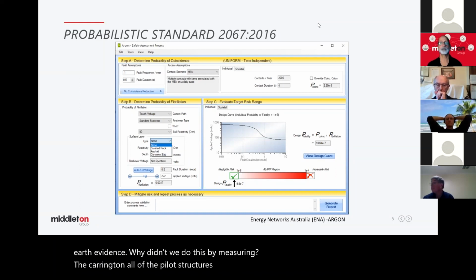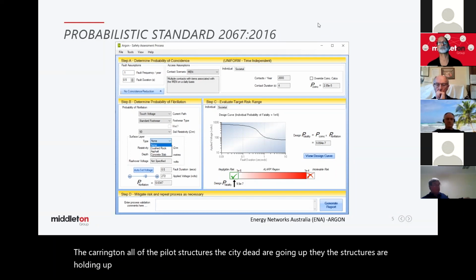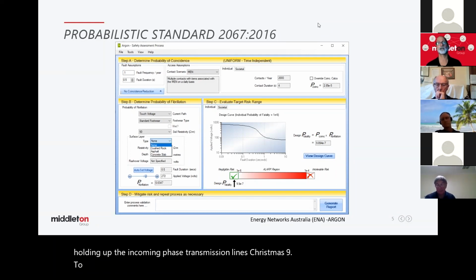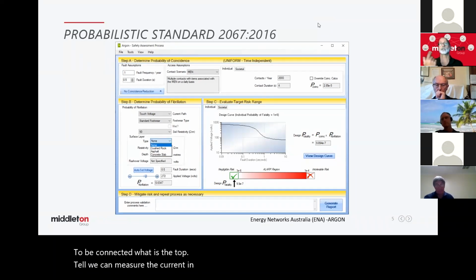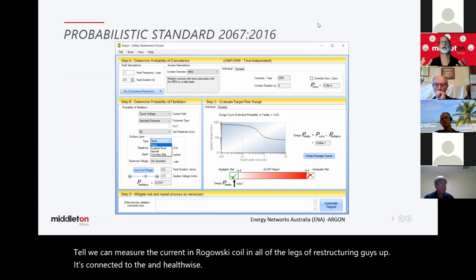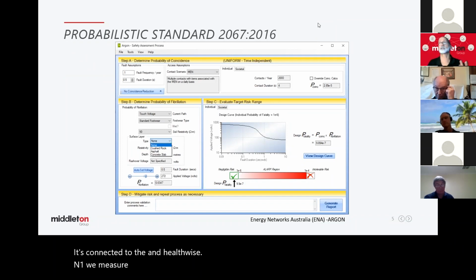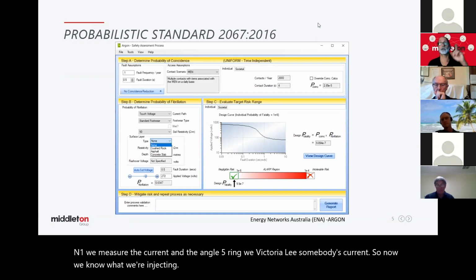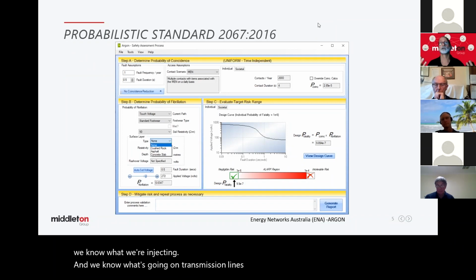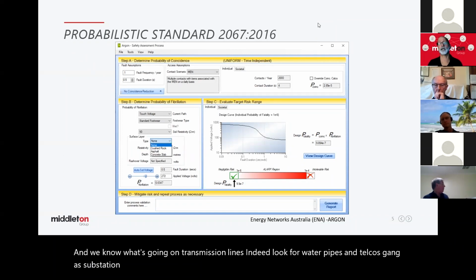So no, we're not going to crawl to the top of the transmission tower and measure the current going in the overhead earth wire there, but we do this by measuring the current in all of the high voltage structures that are holding up the incoming phase transmission lines, distribution lines. They'll be connected to these overhead earth wires at the top. So we can measure the current with a Rogowski coil in all of the legs of every structure that's connected to the overhead earth wires. And we measure the current and the phase angle, and we vectorially sum these currents. So now we know what we're injecting and we know what's going out along transmission lines. Indeed, we look for water pipes and telcos going out of the substation. They should all be isolated, obviously, and have no current in them.